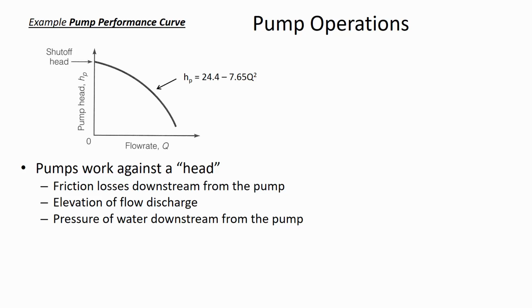Okay, this is a really important figure. It is a typical pump performance curve, and there are a lot of pump problems on the FE exam, by the way. So this is important stuff. What this shows is that as you increase the flow rate that a pump is called upon to achieve, the amount of head that it can add to the system decreases. So it's like a balancing act. The pump can add a lot of head, or it can achieve a high flow rate, or somewhere in the middle it can do a little of both, but it can't do everything, not all at once.